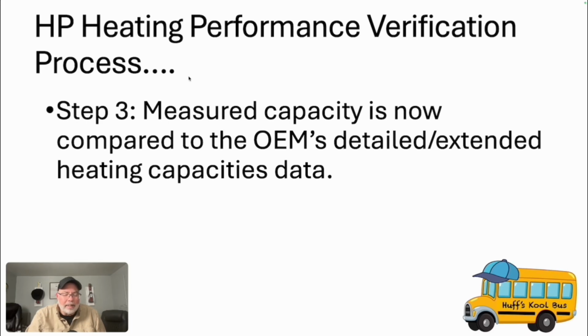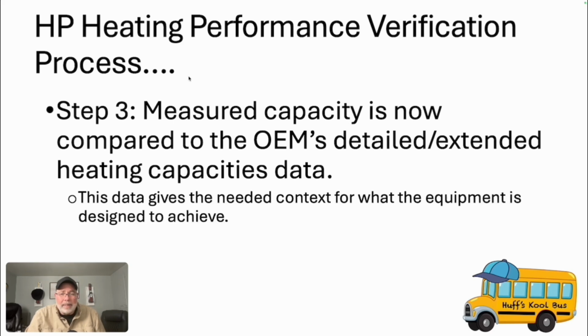Then step 3, this is the part that I don't see other people talking about. And this is what I learned working for the OEMs for those years, right? So we measured the airflow. We now measured the delivered capacity using those airflow numbers that we took. Now we're going to compare that to what the OEM says the system should be doing. In other words, we're not guessing anymore. This data gives you the needed context for what the equipment is designed to achieve.